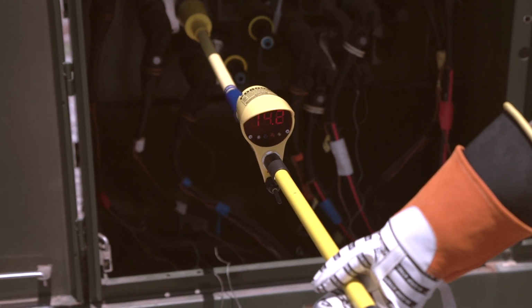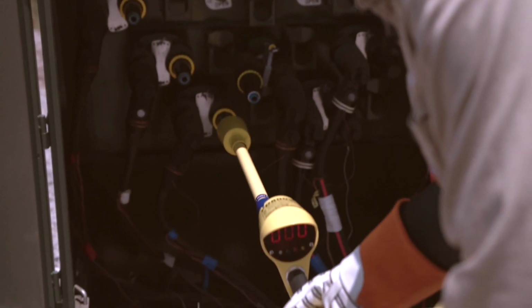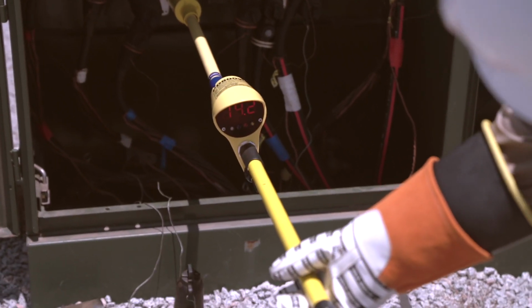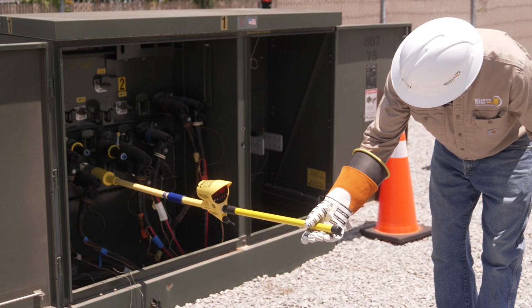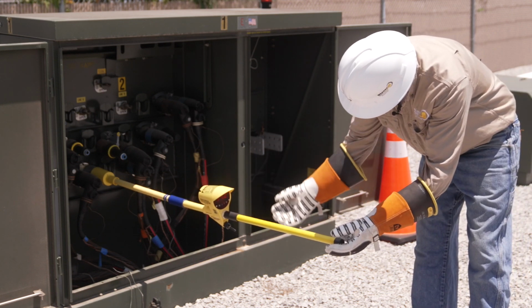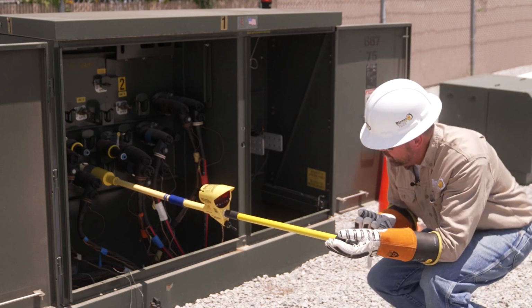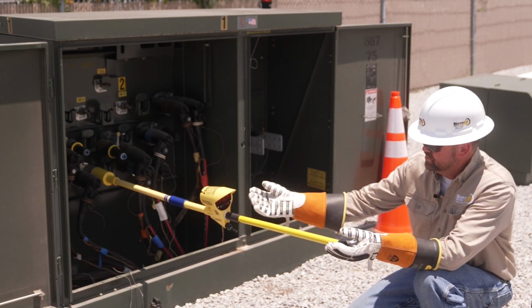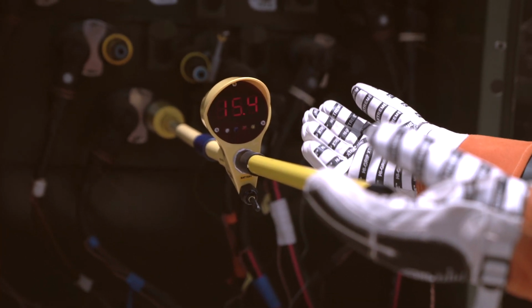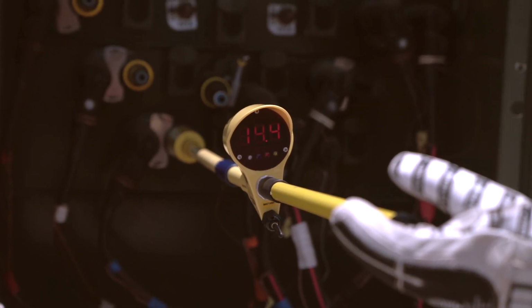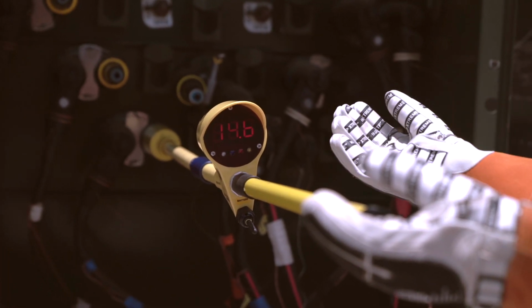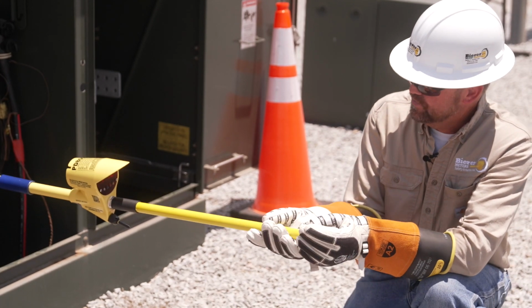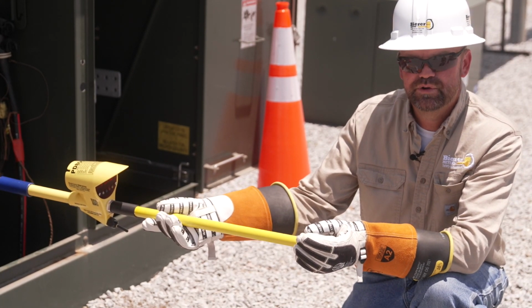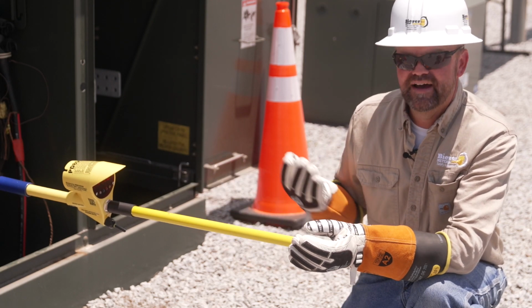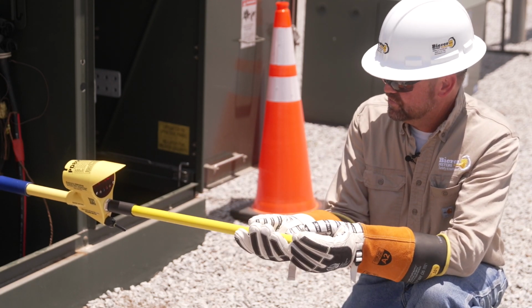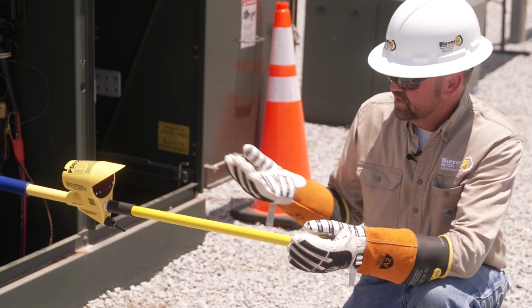I have 14 kV again, 14.2. I'll check my third phase, and again I have 14.2, which would be more common to have a slightly higher reading because now I'm working down closer to earth. And in fact, since I'm a ground plane, if I approach this device, you'll notice when my hand gets close to this housing, that reading goes up. It's going up because I'm a ground to this device. So it starts coupling with me. So I don't want to short stick this device because the reading will go up. I don't want to approach this device with my body because the reading will go up. So keep your distance from this tool, again, about 2 feet or so, just so it doesn't adversely affect the reading.